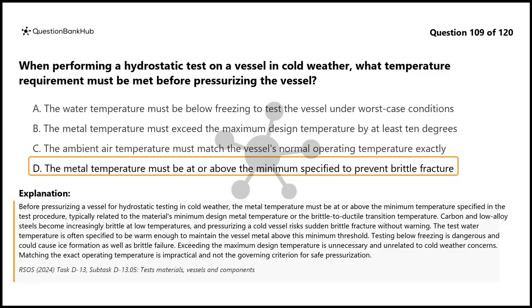The test water temperature is often specified to be warm enough to maintain the vessel metal above this minimum threshold. Testing below freezing is dangerous and could cause ice formation as well as brittle failure. Exceeding the maximum design temperature is unnecessary and unrelated to cold weather concerns. Matching the exact operating temperature is impractical and not the governing criterion for safe pressurization.